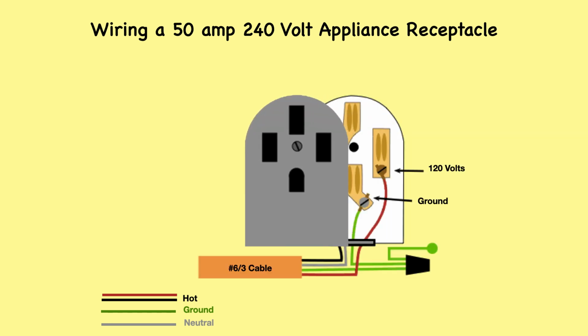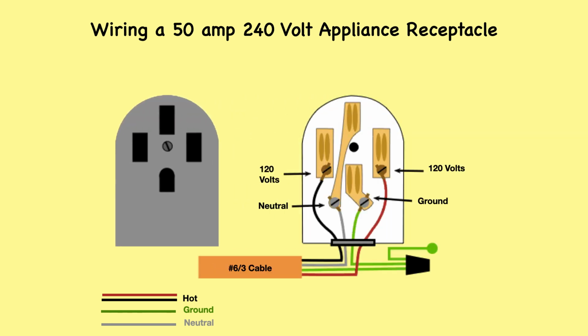This wiring diagram is used for 50 amp appliance outlets. The receptacle should be wired to a dedicated 50 amp circuit breaker, using number 6 AWG cable wire. The 50 amp circuit is required for new installations of some large appliances requiring 240 volts. Two wires carrying 120 volts each can be combined to provide high voltage to heating circuits, and one of the 120 volt wires can serve lights or other low voltage circuits in the appliance. The neutral wire provides a return path for the circuit, and the ground wire provides extra protection not found on older 240 volt appliance hookups.